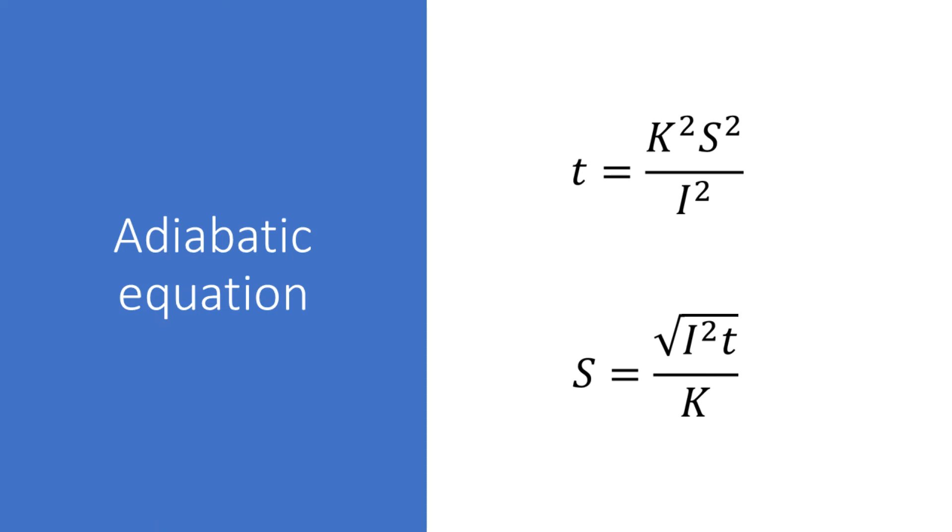One thing to bear in mind though is that the time current characteristics stop at 0.1 seconds which is instantaneous, however in most cases the fault currents will be greater than the minimum required to meet the disconnection time. This is good from the point of view that it will operate the device within the disconnection time, however it's also necessary to ensure that the conductor is capable of withstanding the actual fault current even for that 0.1 of a second.